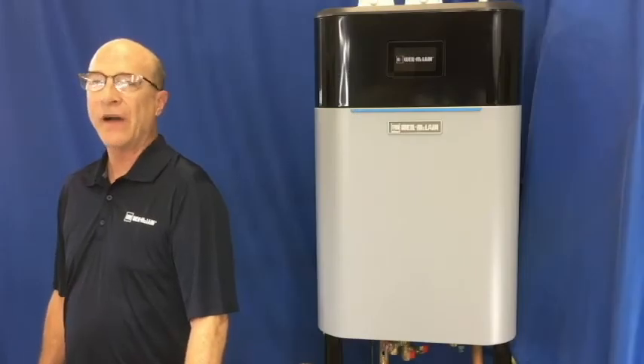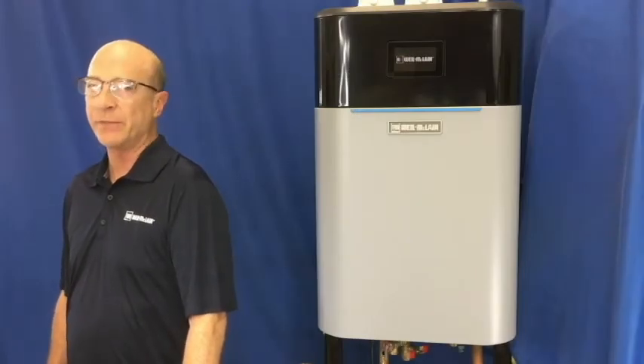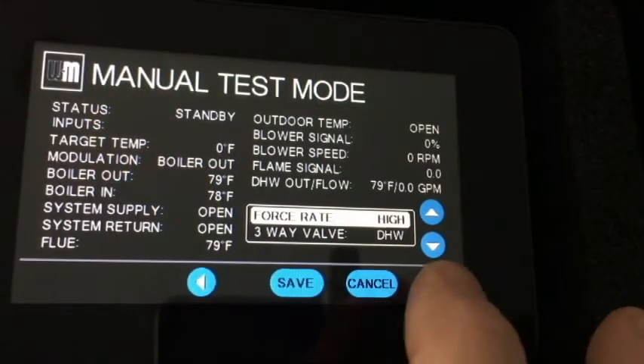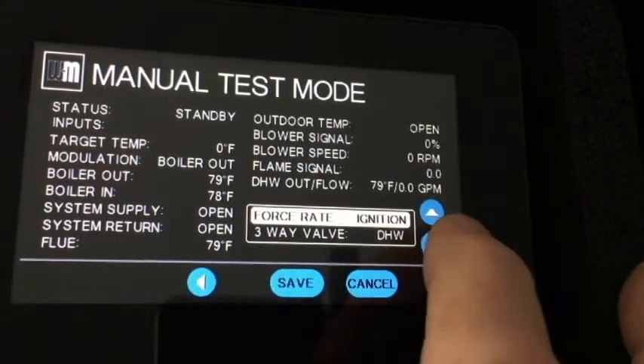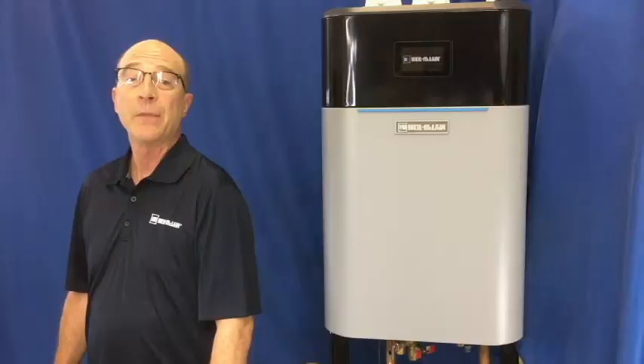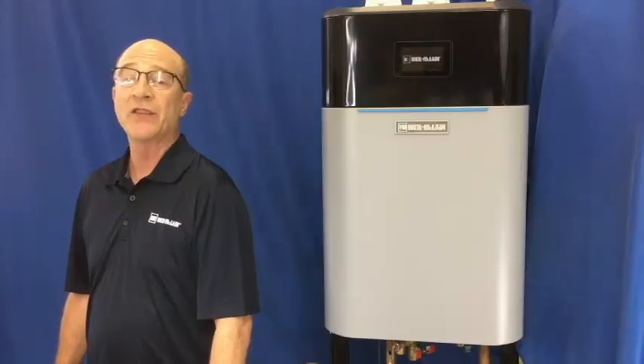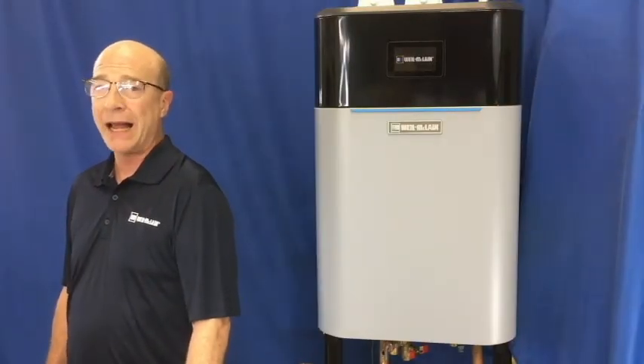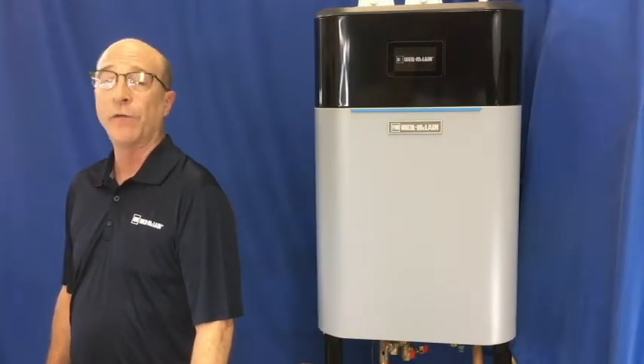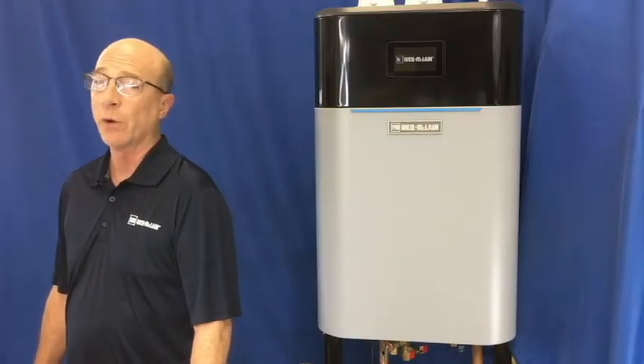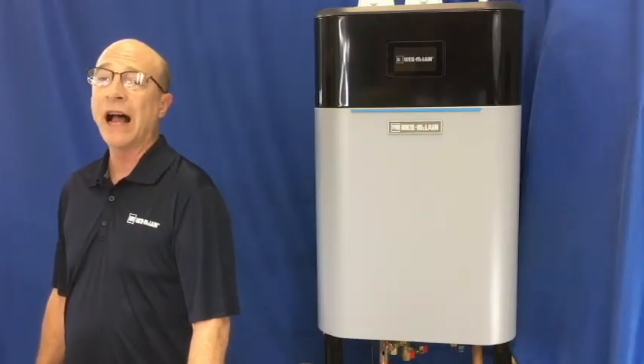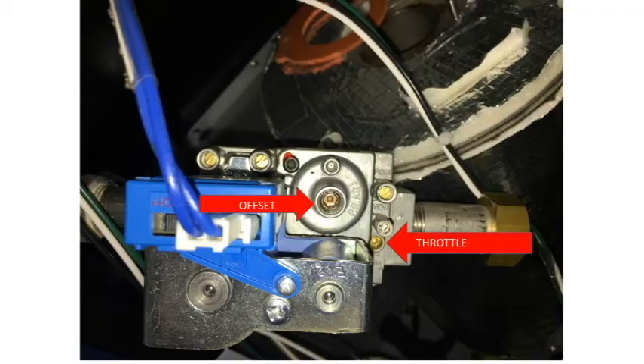Once the high fire setting has been set, push the down arrow button until you see low, then press save. The boiler will ramp down to the low fire setting. Remember, throttle for high fire, offset for low fire.